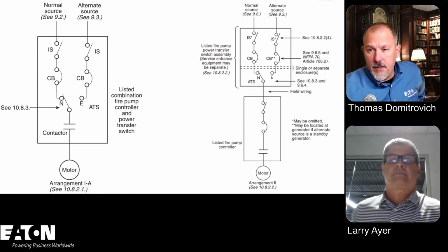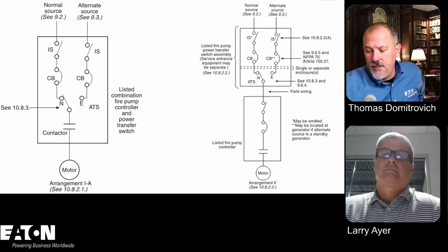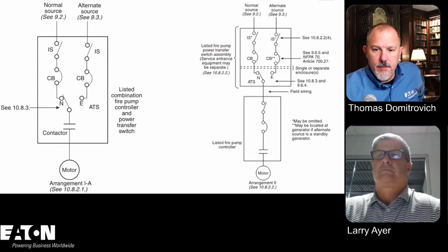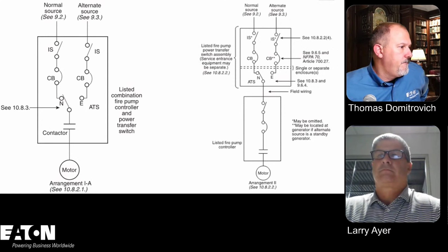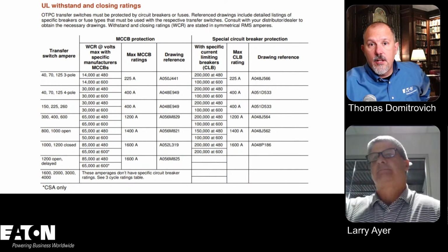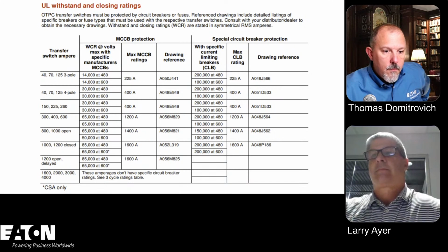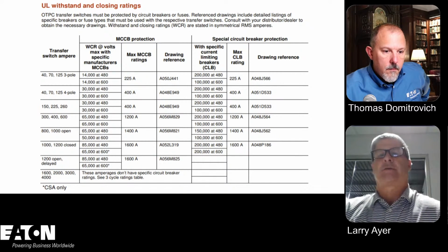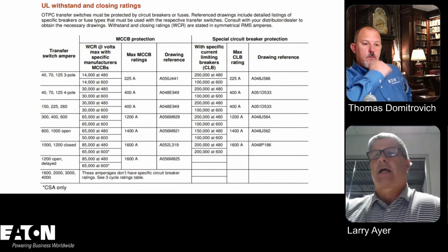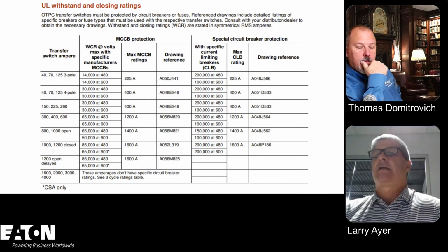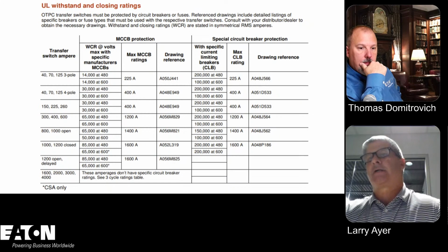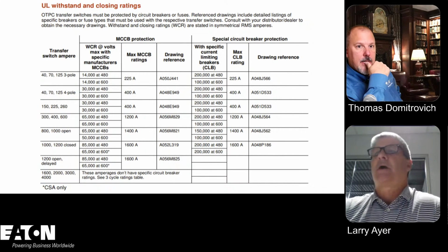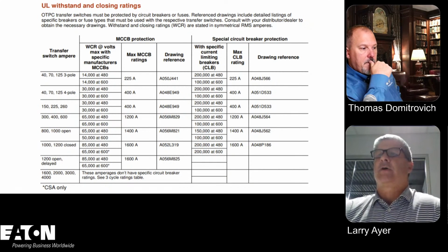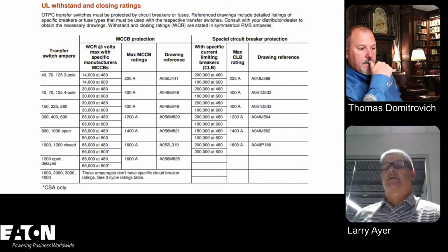Yeah, and all of that can be listed as service entrance rated too. So that's another little aspect you've got to keep in mind as well. And then you've got the withstand and closing. There's a question there for fire pump, a source of fault current. I think a fire pump is a source of fault current. Again, you've got to look at some of the ways I was taught: if the motor's 50 horsepower or greater, sometimes you multiply by 4 to get the amount of fault current that would contribute back to the fault. If it's less than that, I was taught to ignore that.